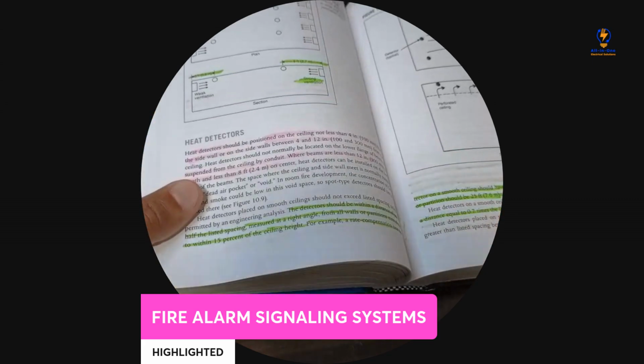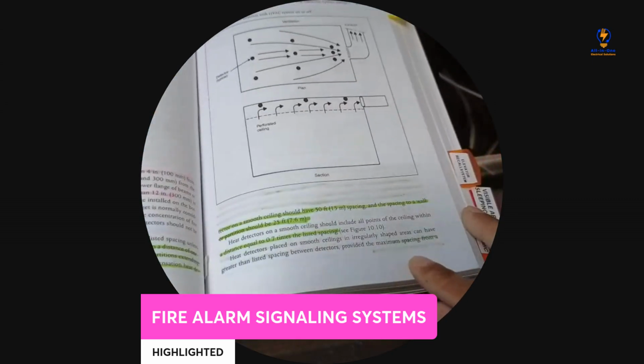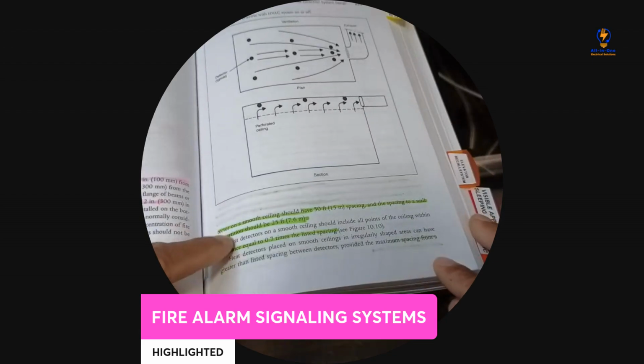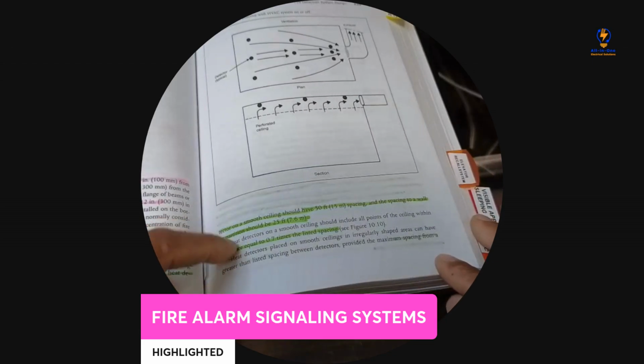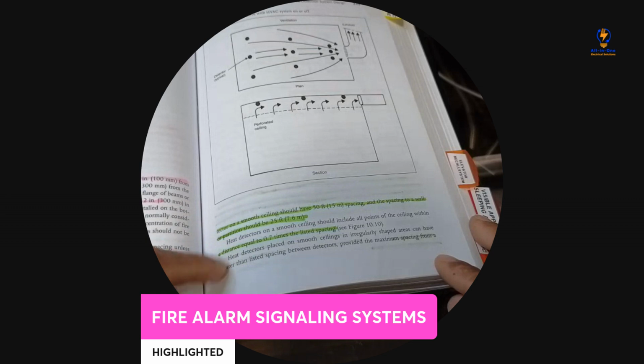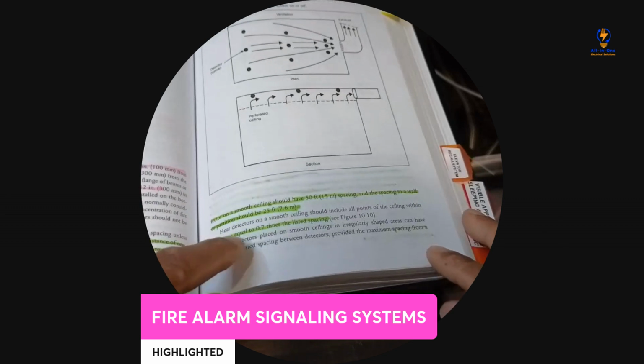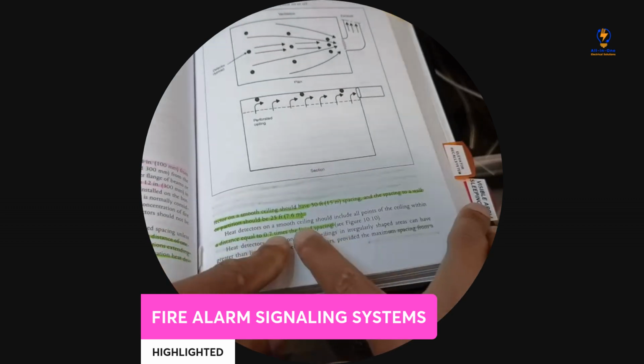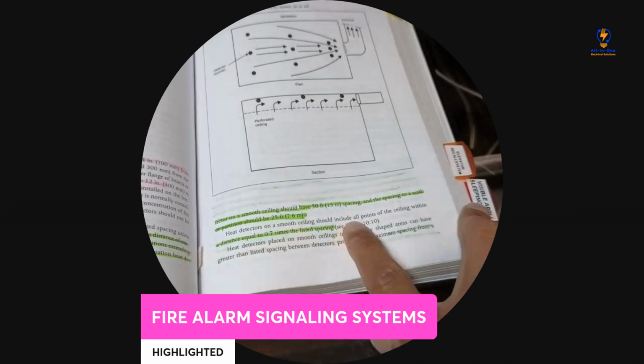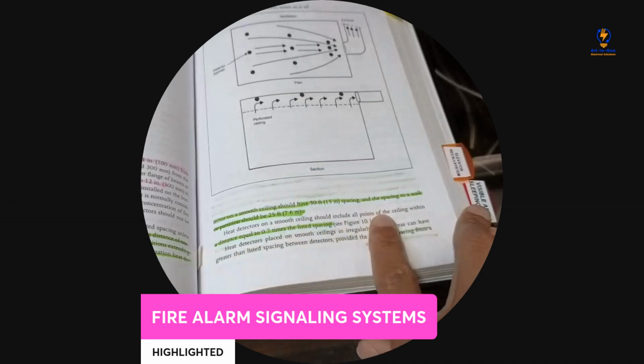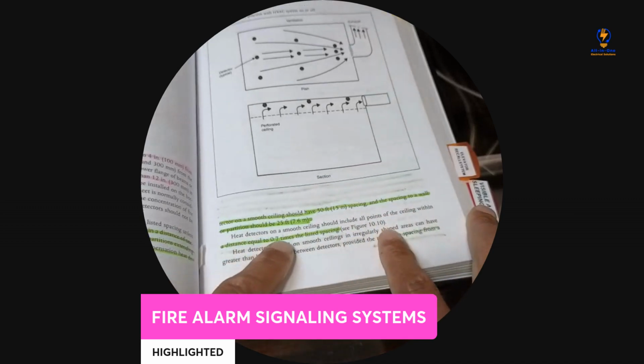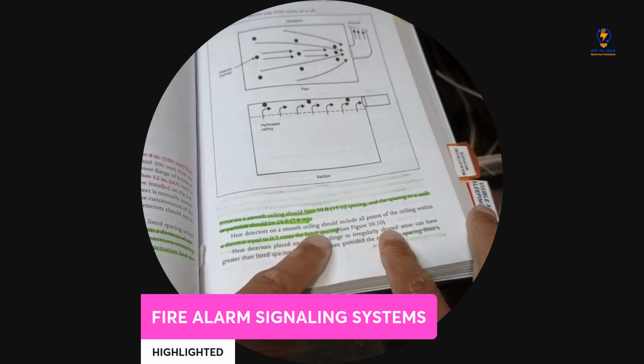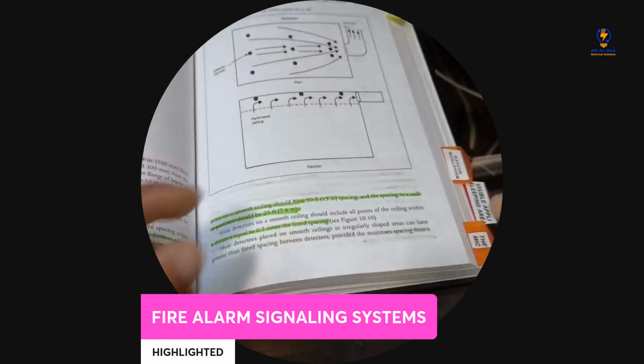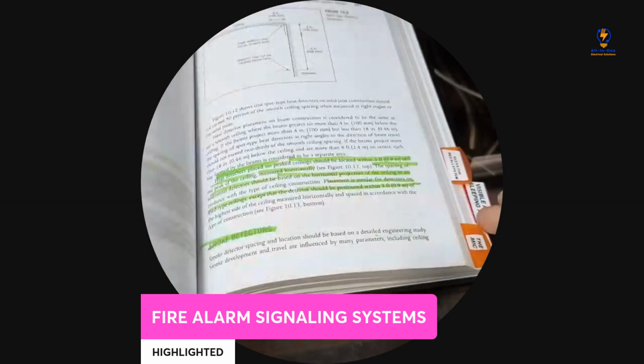We are in 238, we're passing to 239, and then you're going to highlight these two lines as well. And as you see here, all of these numbers right here: heat detectors on a smooth ceiling include all points on the ceiling within a distance equal to 0.7 times the listed spacing. Very, very important, guys. Okay.